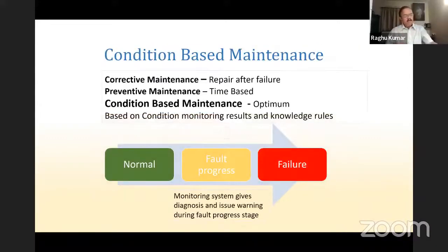Next, we move on to condition-based monitoring. Before condition-based monitoring, let us see what the types of maintenance are. One is corrective maintenance, where the repair is only after failure. Preventive maintenance is an old system where time-based maintenance was carried out, and fixed time-based things were maintained. The issue was we were overdoing it. Maintenance was being carried out without knowing the internal condition. It was just routine maintenance.